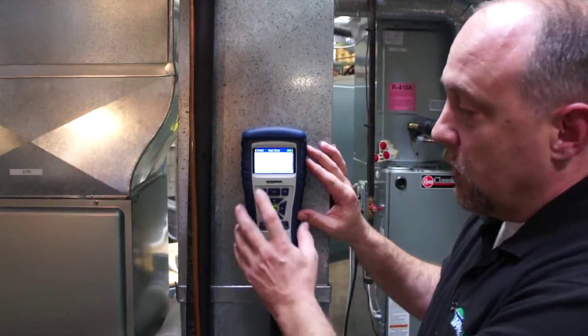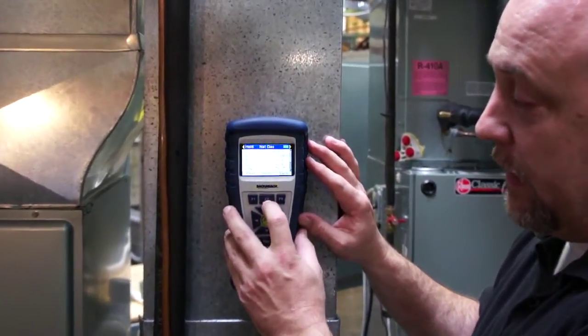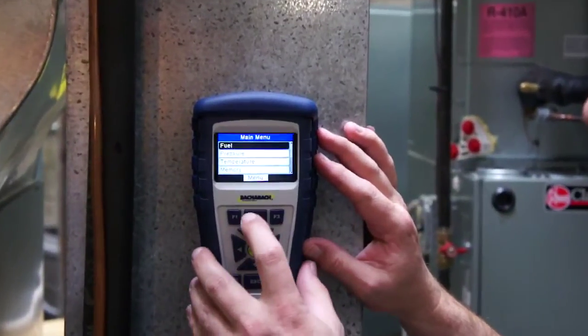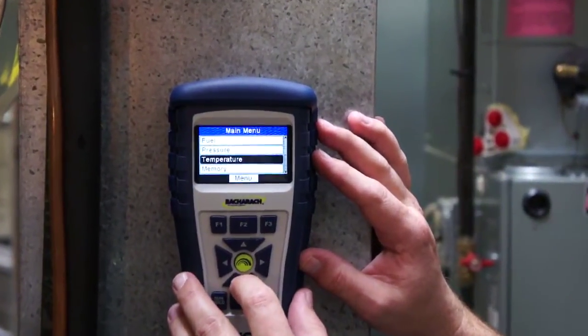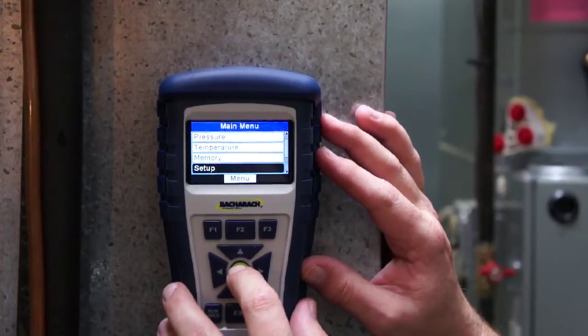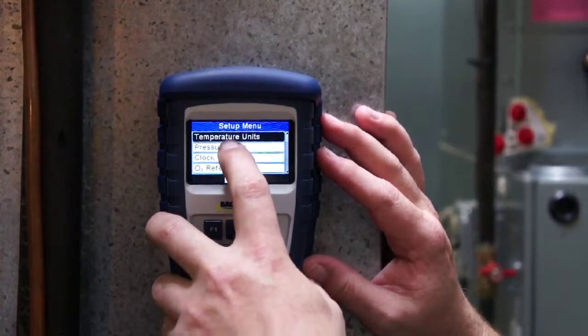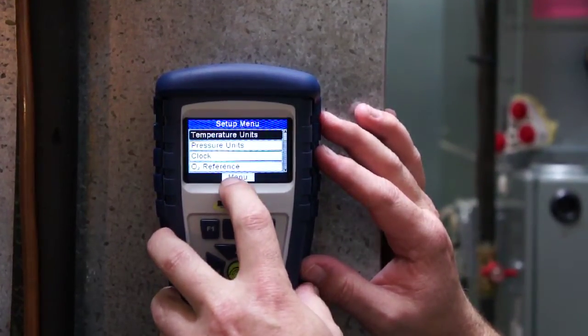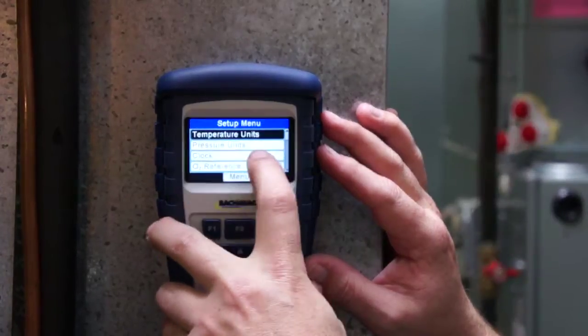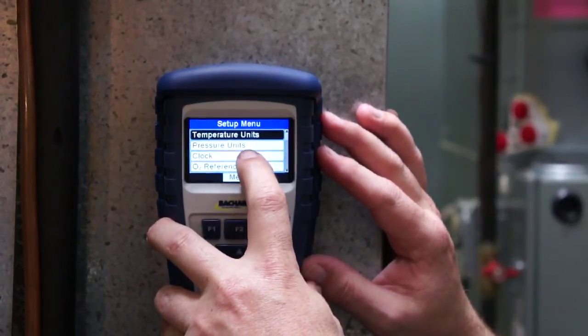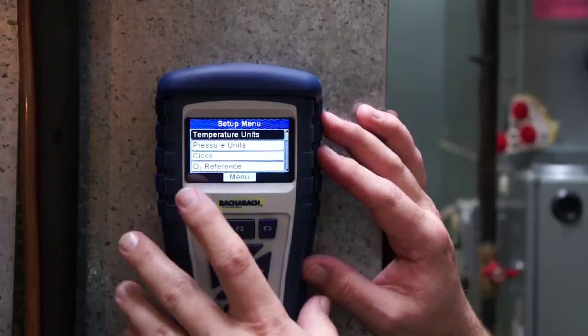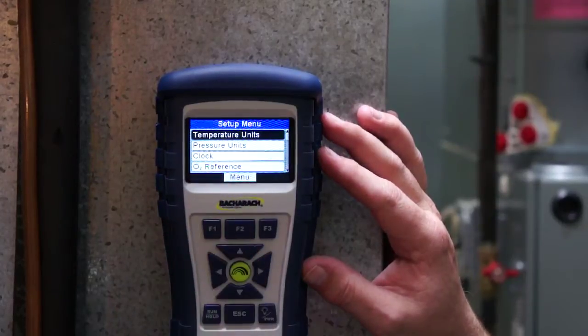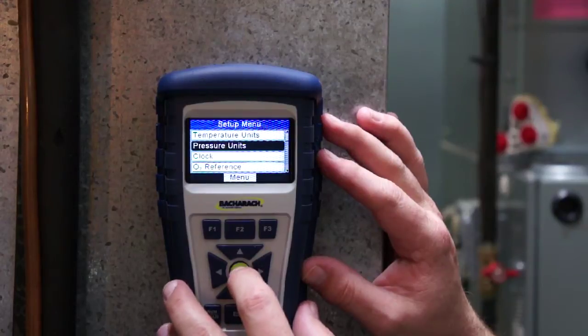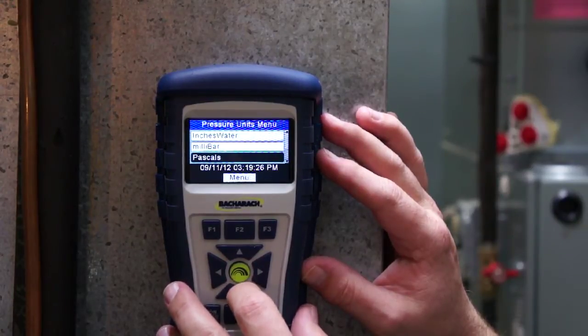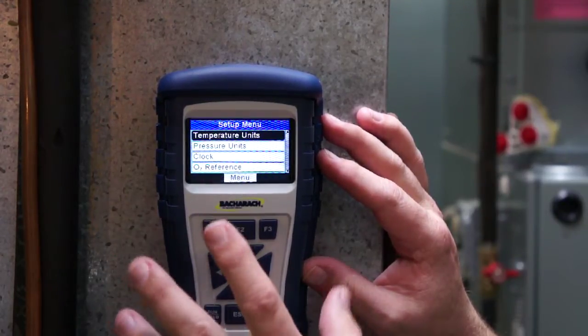So if you go in and you hit the menu key, which is the F2 key, and I go into the setup here, scroll down to setup, hit enter, I can go through and I can configure any one of these units. So I got temperature units, which comes factory set at degrees Fahrenheit. My pressure units, which is factory set at inches of water column. If I'm in energy auditing and I want to change it to pascals, it's simple enough to do. I just go into pressure units, hit enter, scroll down to pascals, hit enter, and now it's configured.